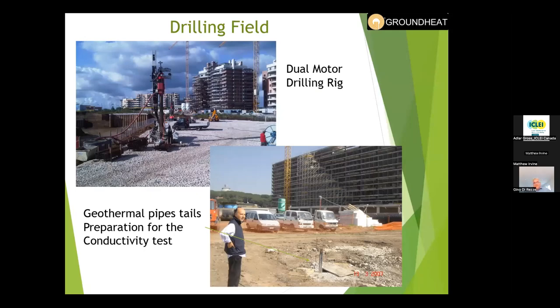On the bottom right, you'll see the test hole. They were to put the conductivity test there in 2007. Again, we were using conductivity tests for a long time. And on the top left, you'll see dual rotary geothermal drilling machines, which we eventually brought to Canada in 2008. Now the geothermal dual rotary is being used all over our area here, because it allows us to do a hole a day, or maybe a hole and a half a day. Before that, we were doing a hole a week.